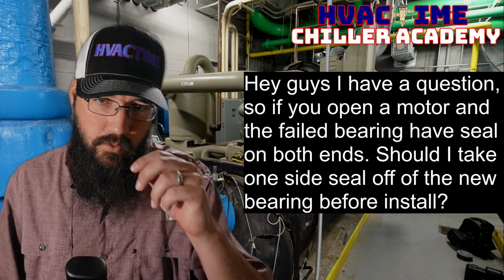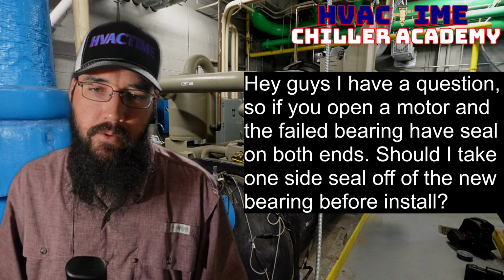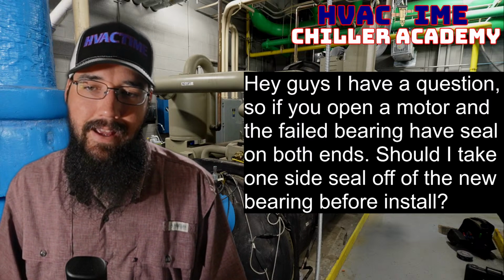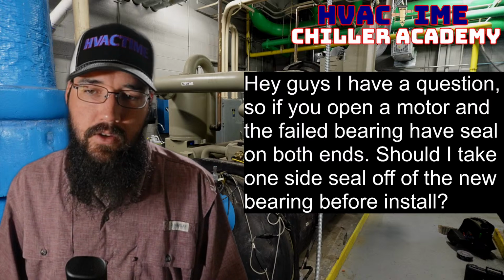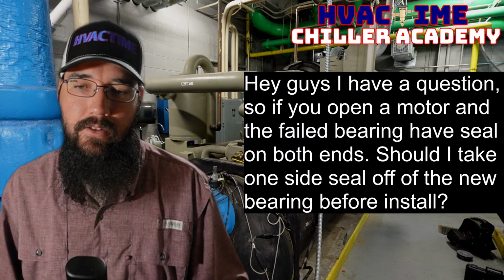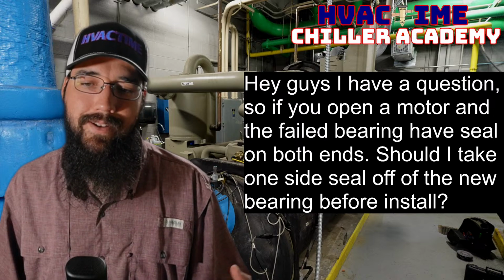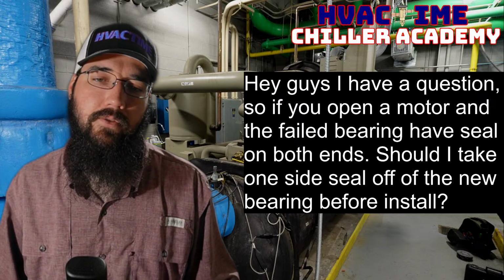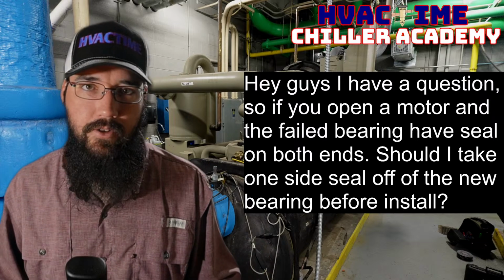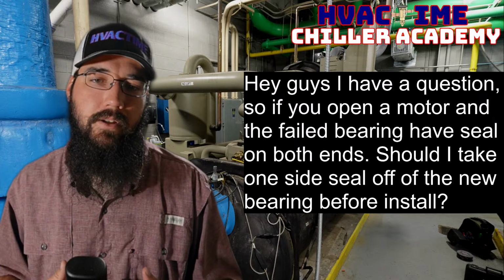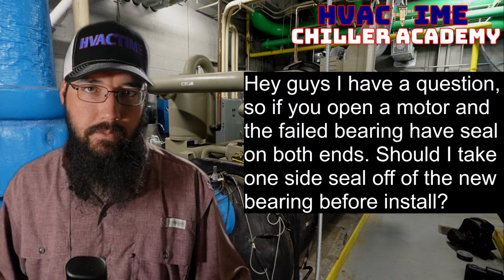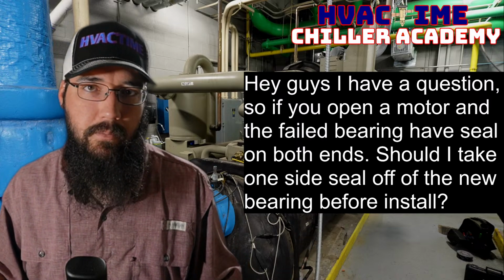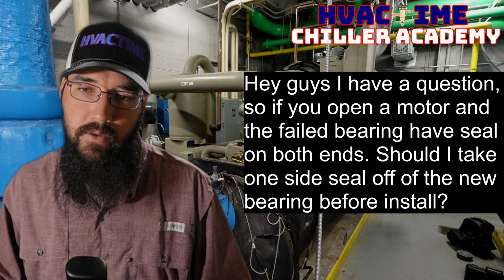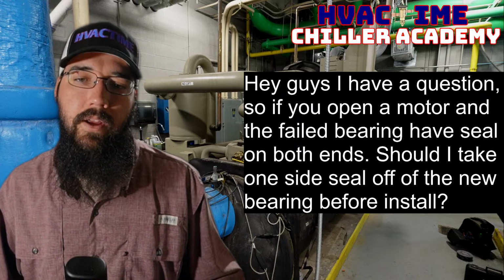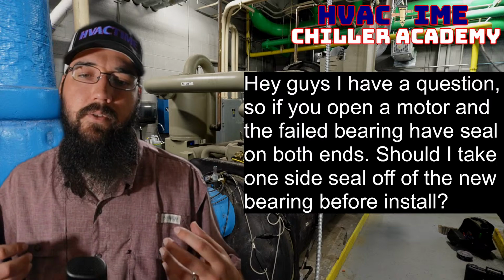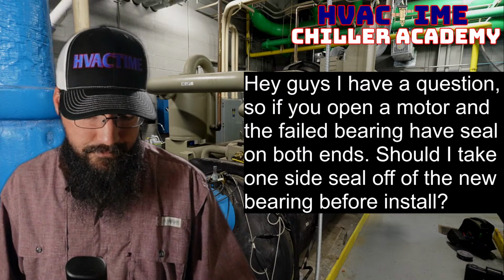Hey guys, I have a question. So if you open a motor and the failed bearing has seals on both ends, should I take one side's seal off of the new bearing before install? Now this is in the context of a standard motor. It could be a pump motor, it could be an open drive motor like we see with a YK. Sometimes we'll do those bearing change outs in the field. I've had to do that before. So if we're going to be doing a bearing change out like that, what do we do?